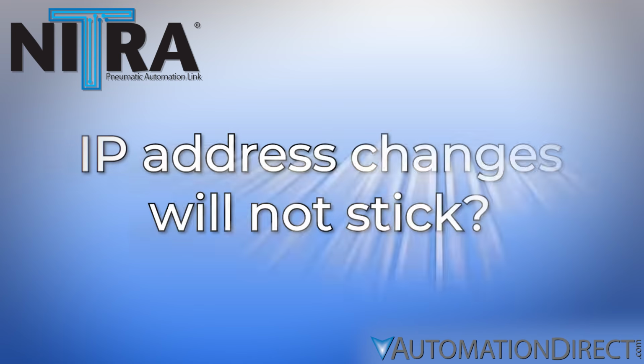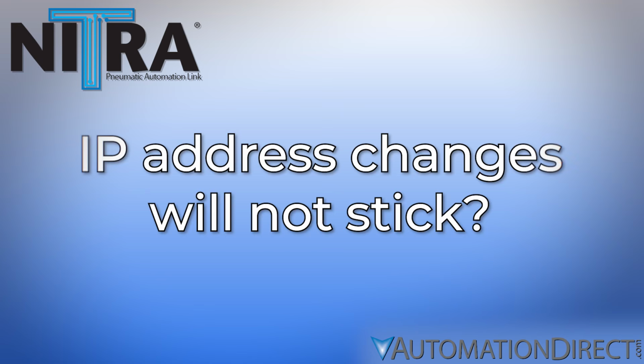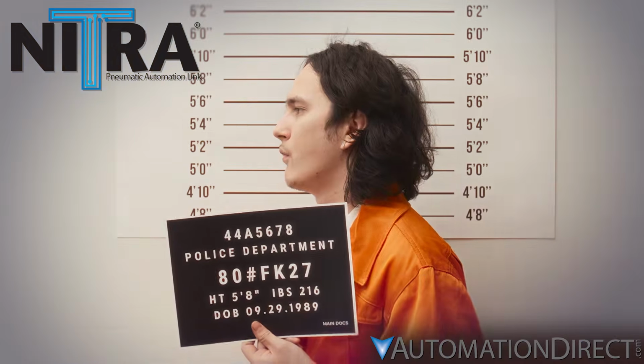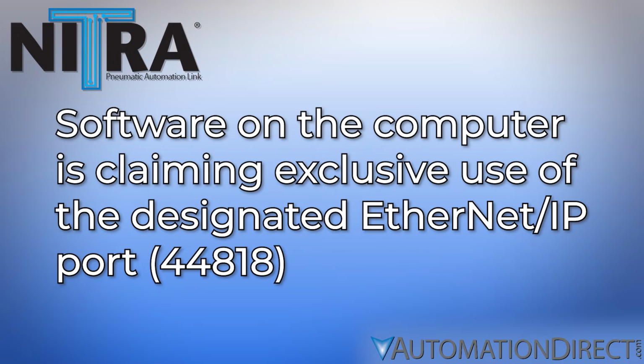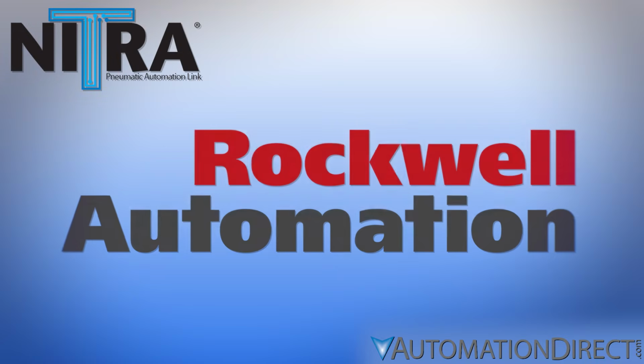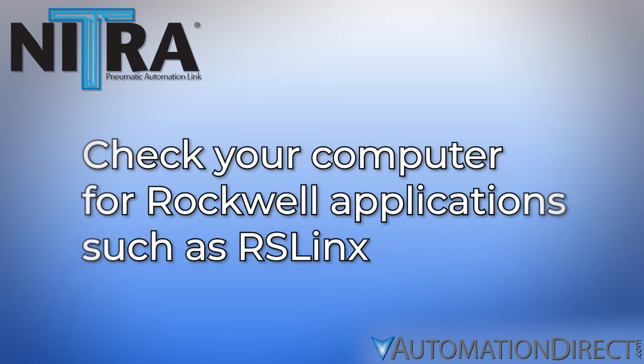One issue that pops up from time to time is that the PAL won't seem to accept an IP address a user is trying to assign. If you're following the IP address setup procedure but can't seem to get the address to stick, there are a couple of things you should check. By far the most likely culprit here is a piece of software running on your computer that likes to claim exclusive use of the designated EIP port, TCP port 44818. The software most known for this kind of behavior is from Rockwell Automation. Check your computer for Rockwell services like RSLinx.